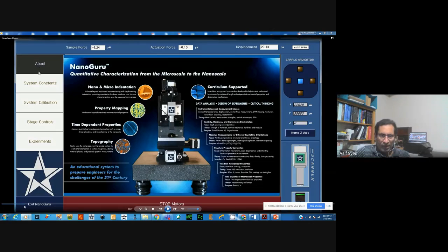When you look at these calibration values, this is a load scale factor, basically a force calibration. This is the displacement scale factor, basically a displacement calibration. This is the electrostatic force constant that I mentioned in my talk: when you apply a voltage, you generate an electrostatic force, and this is the constant in front of that equation. All of this is calibrated at the factory, but we check that for a given transducer all these constants are correct. Once everything is there, we go to the next item.